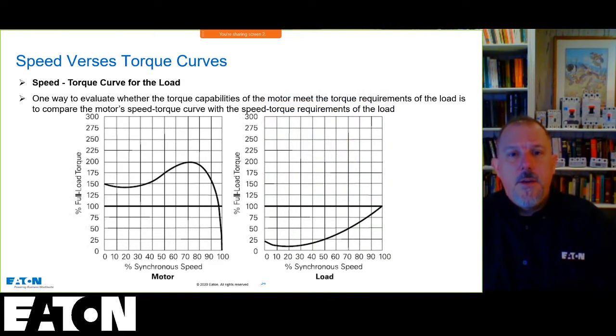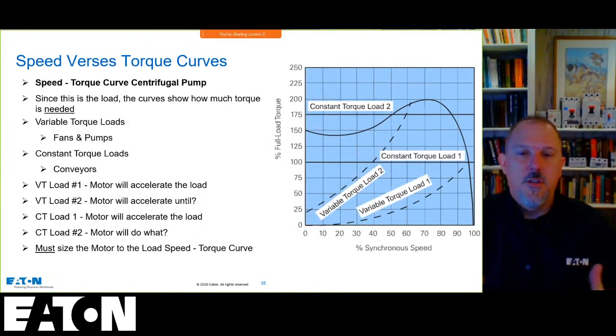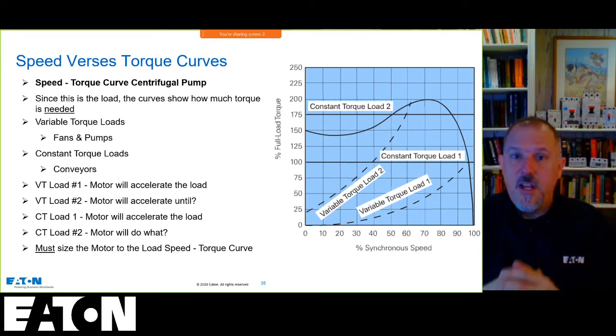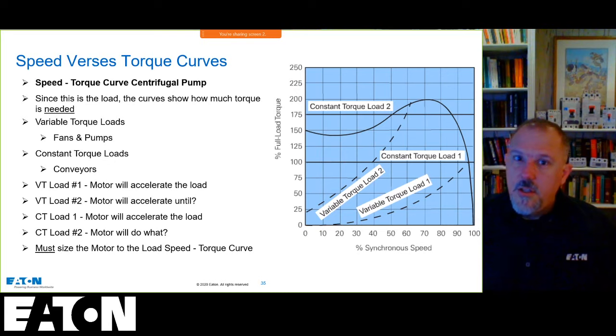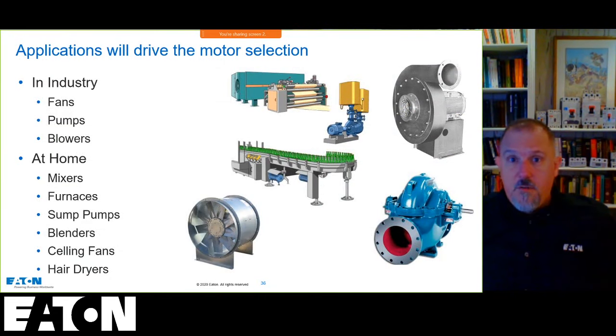And we recognize that a type D, which we'll look at those curves, is important for what they use in elevators. So here's the one curve, which shows you both of those curves, but what happens is the engineer is going to plot that. You can have a constant torque or a variable torque load. For example, that constant torque load number two is an example where your locked rotor torque is less than your constant torque load, and you're not going to move that shaft. It's not going to have enough oomph to get it up to speed. You're not going to get off of zero. So in any case, you have to do that comparison, and that will also tell you how long it's going to take to get up to speed. And we're going to help understand why that's an important parameter when we start picking overcurrent protective devices.